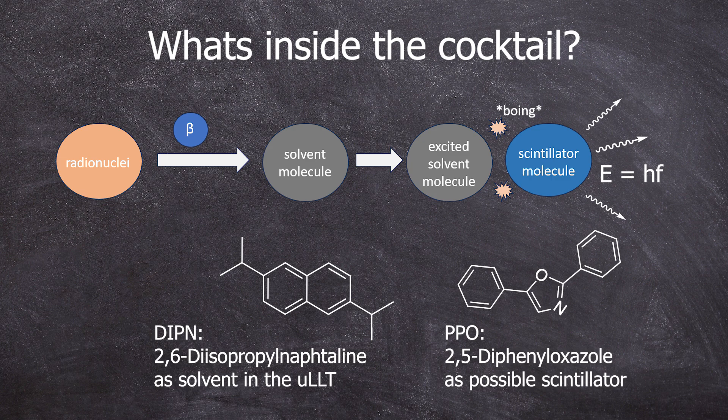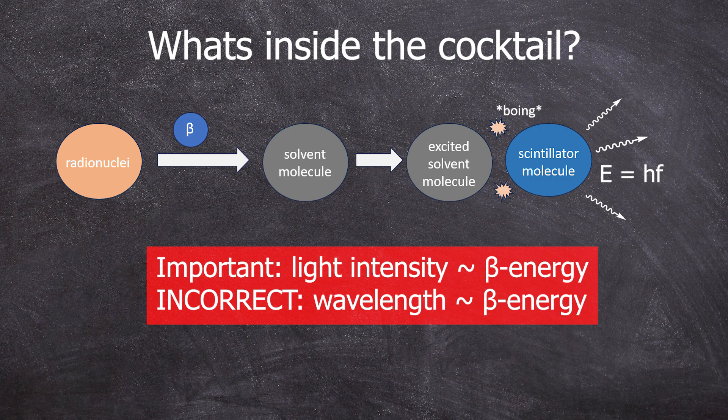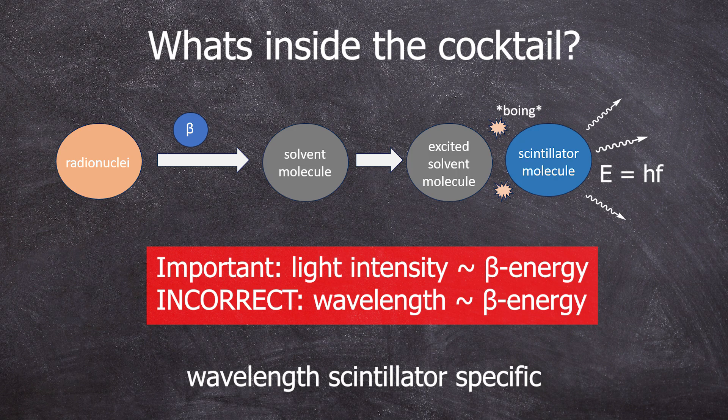The scintillator now releases excess energy in the form of light. A photomultiplier tube amplifies the signal, which is then processed by the software. It's important that the number of photons is proportional to the energy of the beta particle, not the wavelength. The wavelength of the photons depends on the scintillator. In this case, it's in the UV range. I'll come back to that shortly.